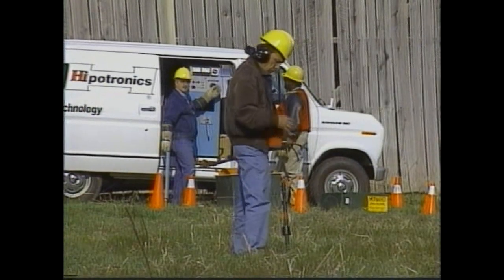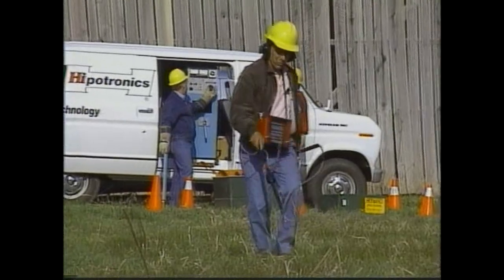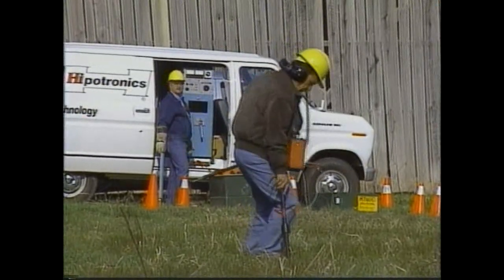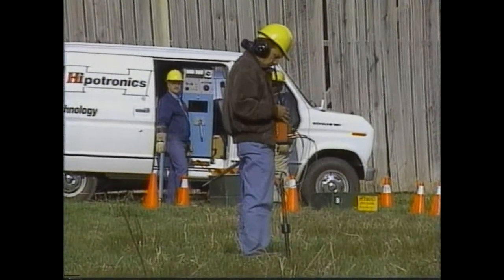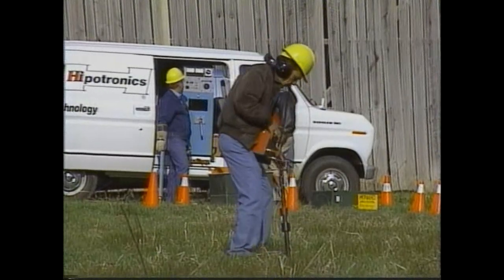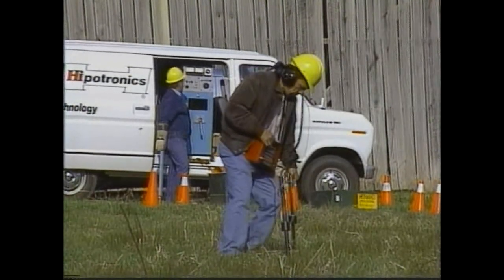If the cable fault is under a trailer house, it's sometimes very difficult or impossible for you to hear, and you'll have to get over the exact point of the fault. One method I use is the wagon wheel locate, like we did with the earth gradient locate. When I reach the position where my sensitivity control is below number 5 on the decal dial, I insert the second probe into the ground and activate its operation switch.